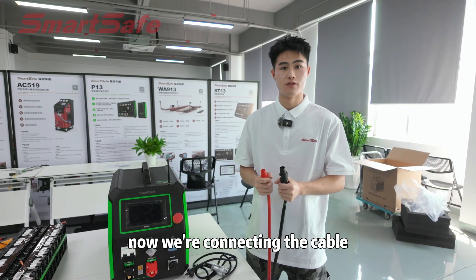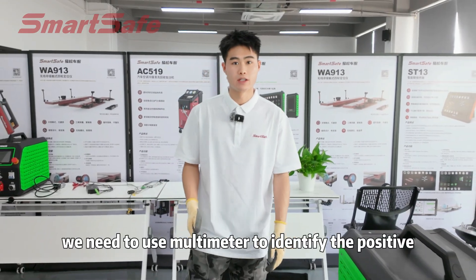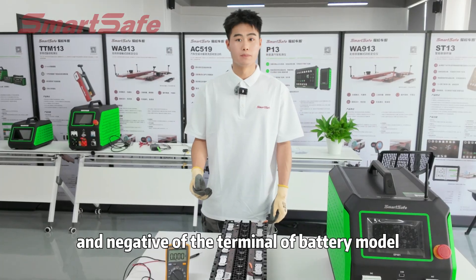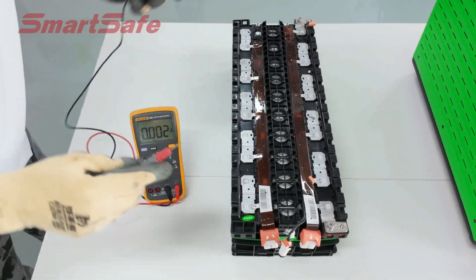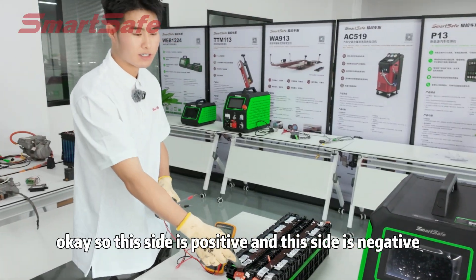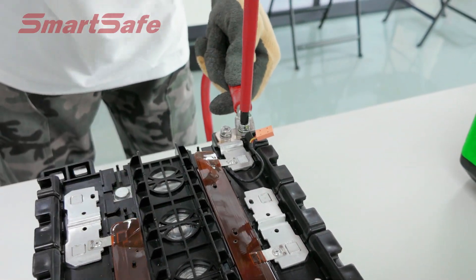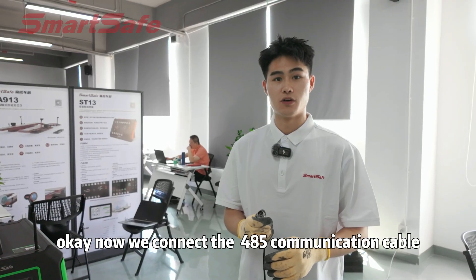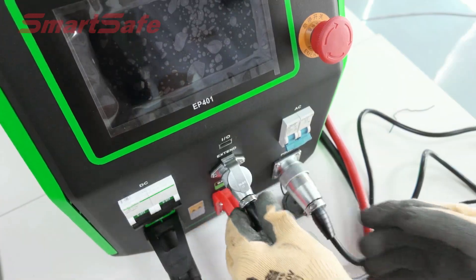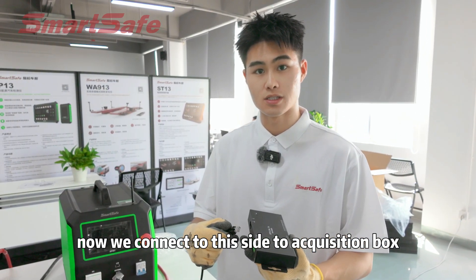First, we are connecting the cable. We need to use a meter to identify the positive and negative terminals of the battery module. This side is positive and this side is negative. Now the red cable connects to the positive. Now we connect the 485 communication cable.